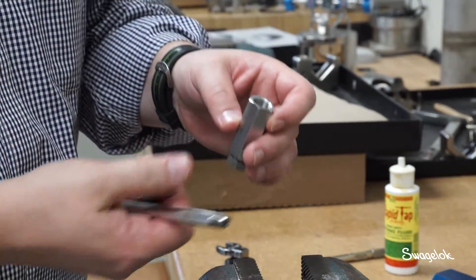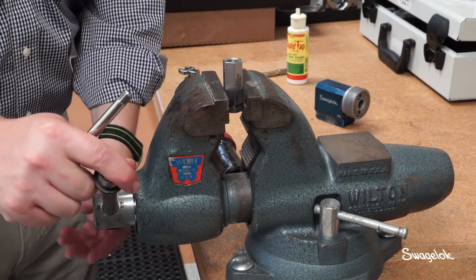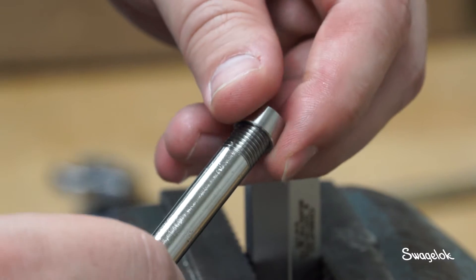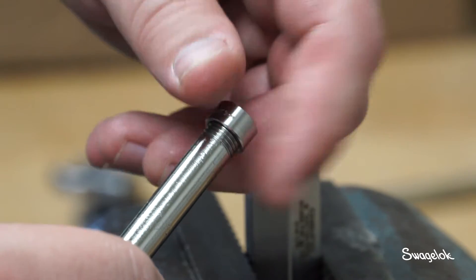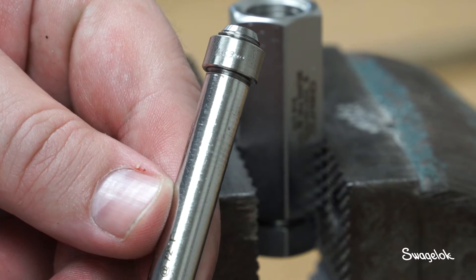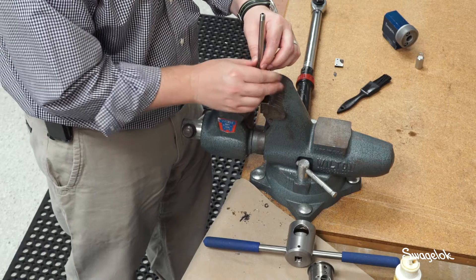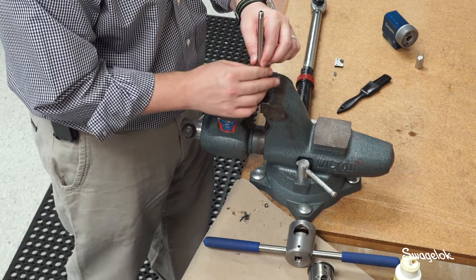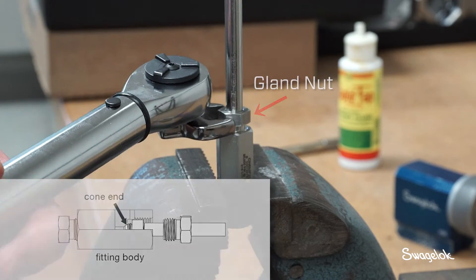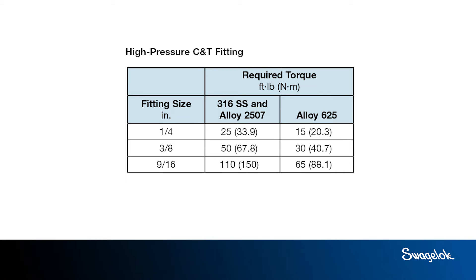Once you have inspected the tubing, you are ready to place the fitting onto it. Place the fitting into the vise. Thread the collar clockwise onto the tubing and continue threading until one to two full threads are exposed at the cone end of the tubing — this will indicate proper position of the collar. Once the collar is threaded onto the tubing, slide the gland nut over the tubing and insert the tubing with the collar into the fitting body. Make sure the cone end of the tubing rests firmly on the angled seat of the fitting body. For medium pressure fittings, tighten to these torque values. For high pressure fittings, tighten to these torque values.